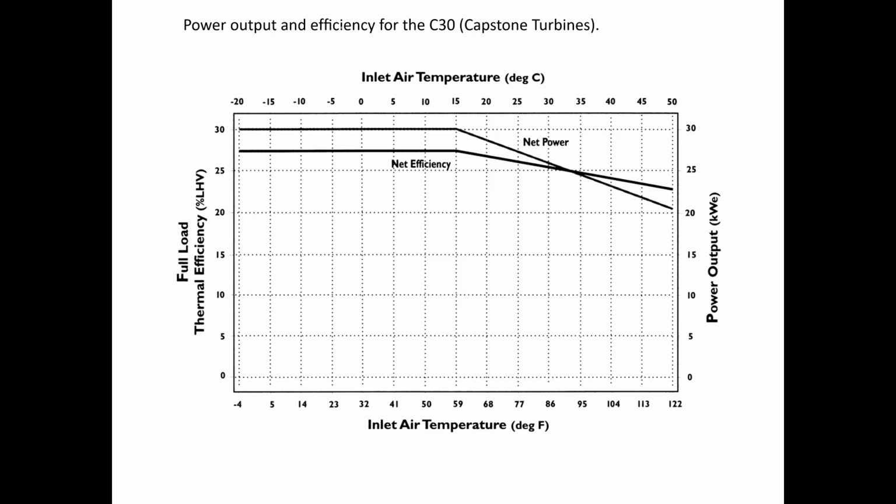You can see here the power output and efficiency as a function of inlet air temperature. Again, as the inlet temperature increases, you have a decrease in power output as well as net efficiency.